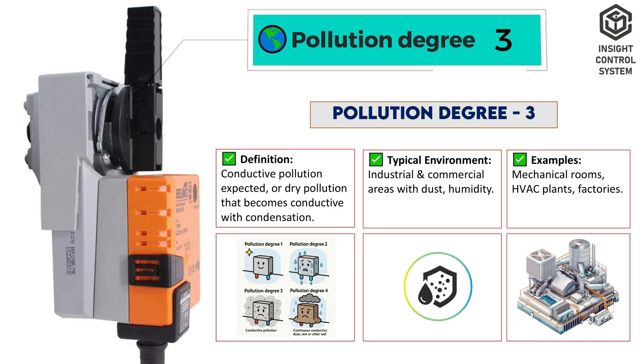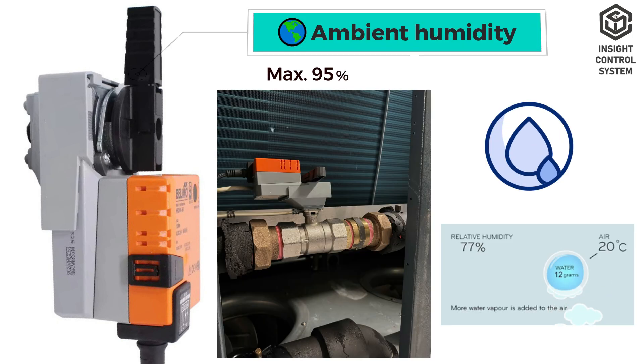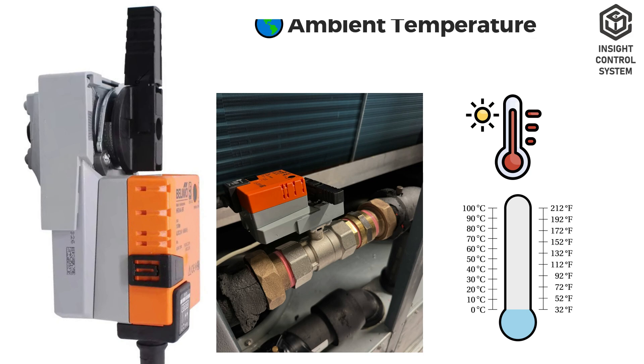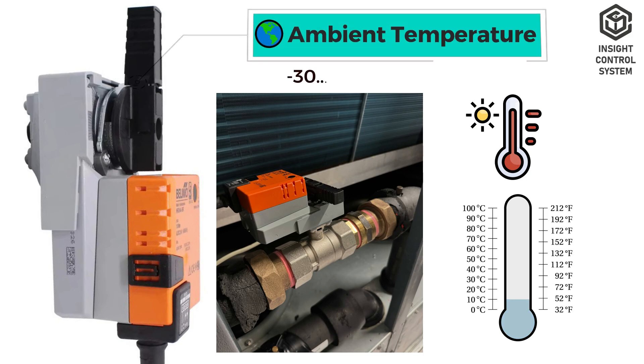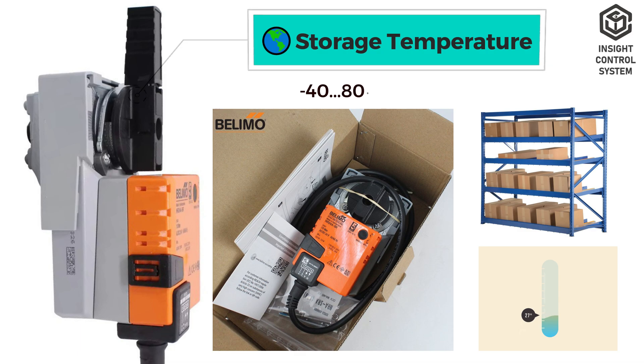Environmental data: pollution degree is 3. Ambient humidity is maximum 95% RH non-condensing. Ambient temperature is −30 to +50°C. Storage temperature is −40 to +80°C.